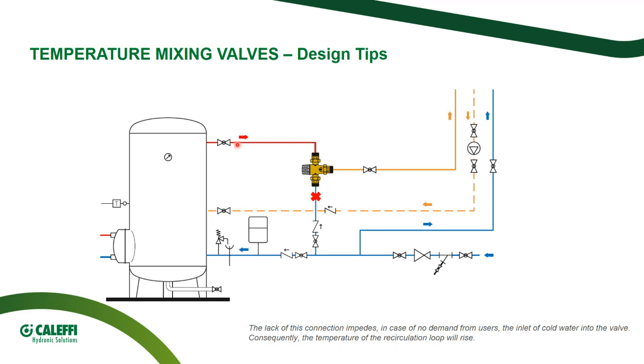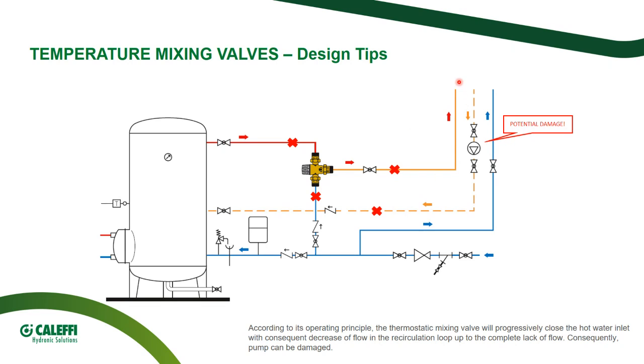So my hot water is circulating and circulating. And there is no demand, so there is no way for new fresh water to enter my loop because nobody is asking for water downwards. If cold water is not entering the loop, the consequence is that the temperature in my recirculating loop will rise. But if the temperature in my recirculating loop is rising, it means that the mixing valve will start closing the hot water inlet.